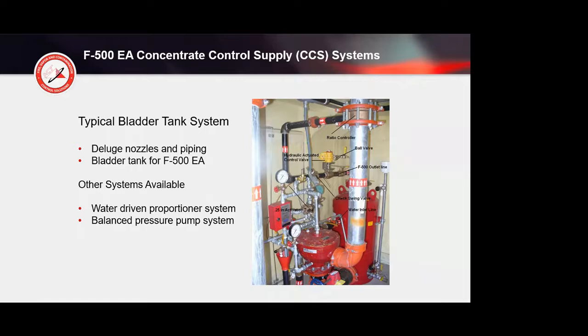So when we supply the system, what we supply is our bladder tank and bladder. We supply this hydraulic actuated ball valve, this yellow thing. We provide the ratio controllers with the proper sized orifice plates. We come on site. We provide filling of the tank, commissioning, startup, and proportioning testing to verify that we're actually proportioning at the designed proportioning rate, not less than design and no more than what's required by NFPA 25. So our package is a pretty comprehensive package, gets sold to the contractor, installed by the contractor, and then we come out and do the commissioning and startup service.